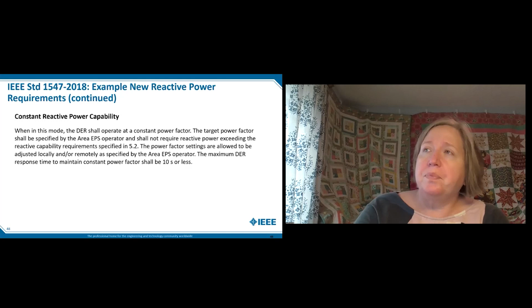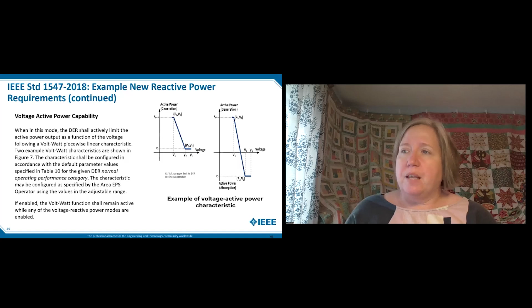So, volt-watt. It's a slightly different piecewise linear curve. And so it can also be adjusted. And as I stated, the volt-watt can remain active while any of the voltage reactive power modes are enabled. To give you an example of that, here at PGE, our default settings for inverters that we don't study is that they have volt-var as the reactive power mode, and then they have volt-watt also enabled. So we can have both of those enabled at the same time.